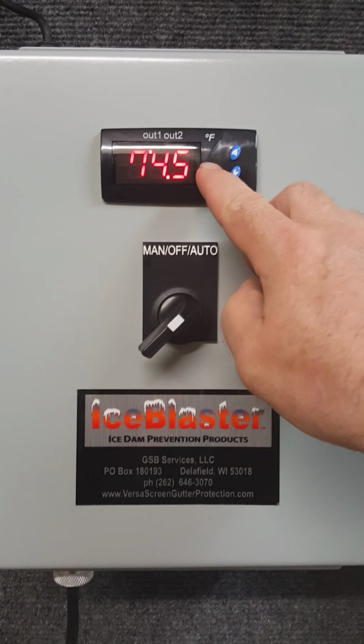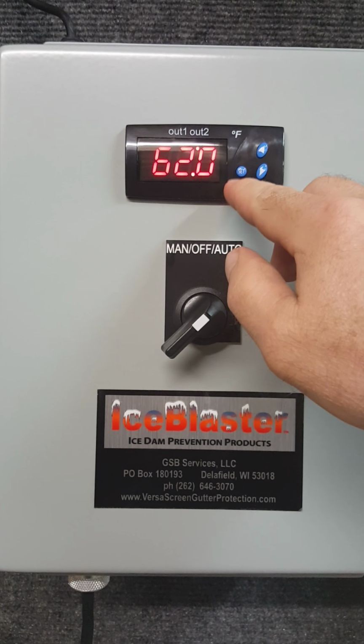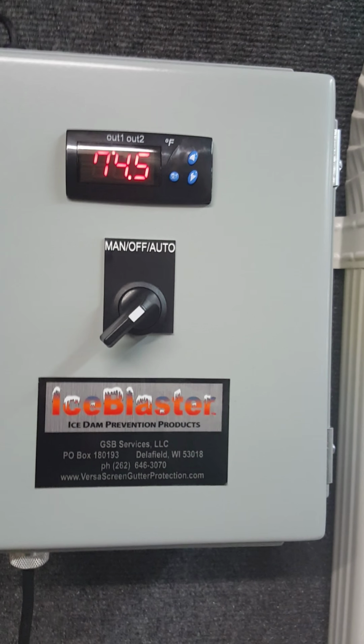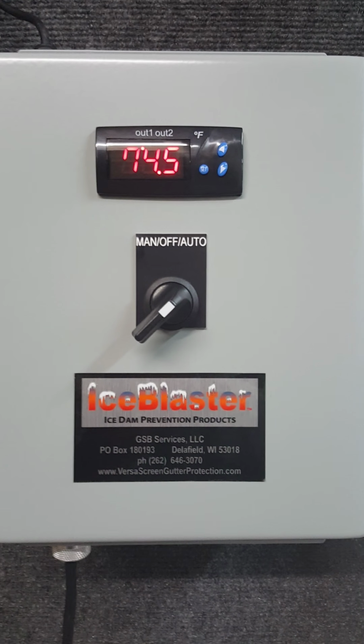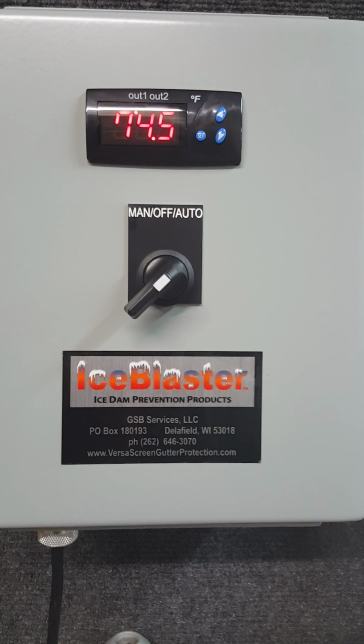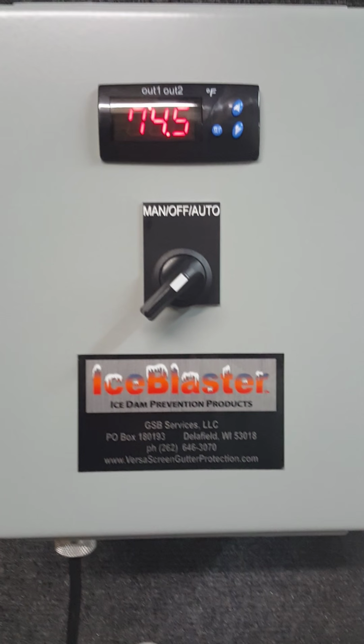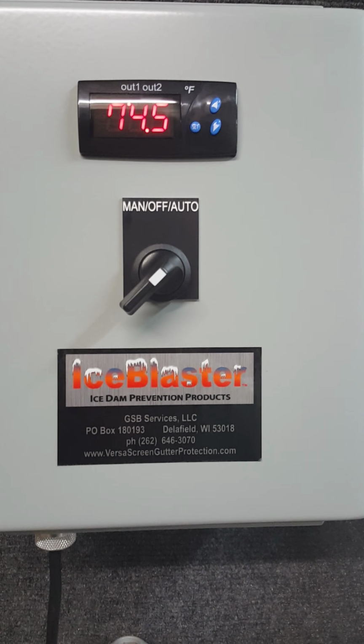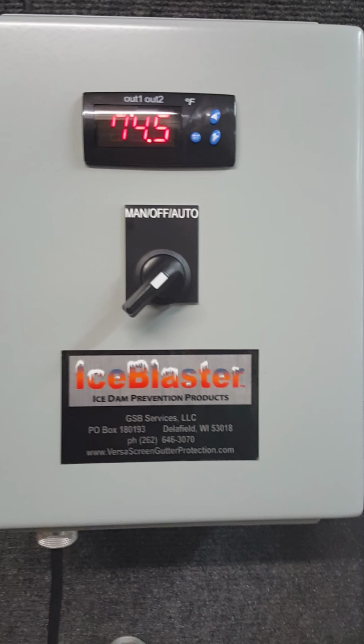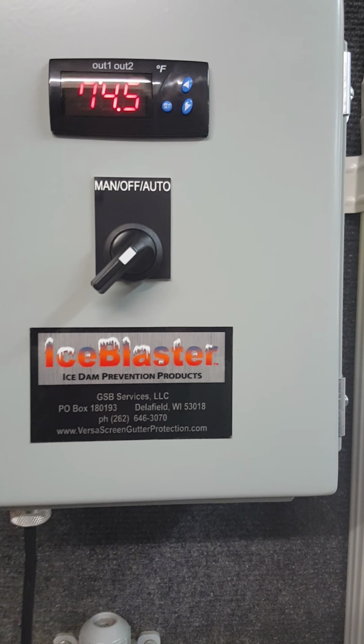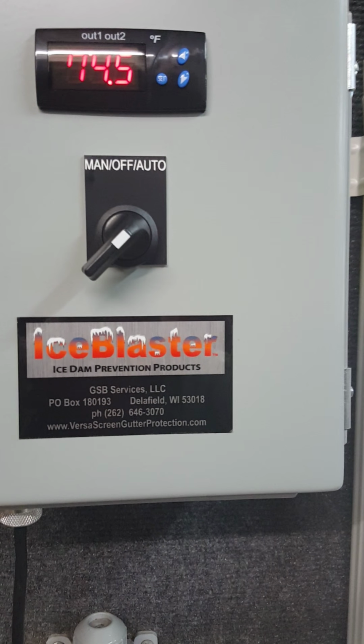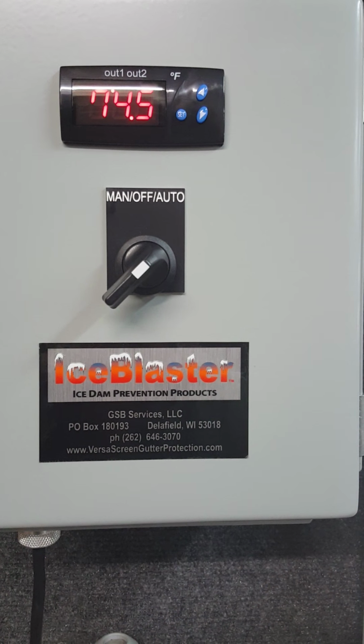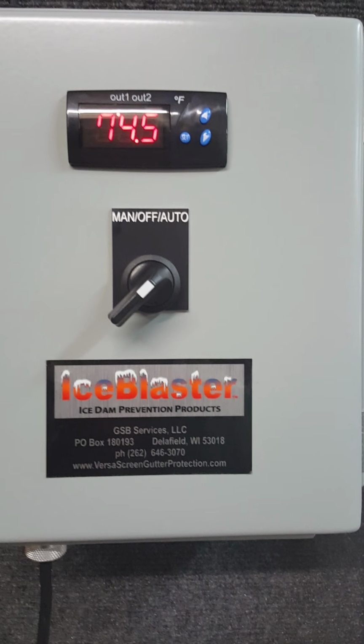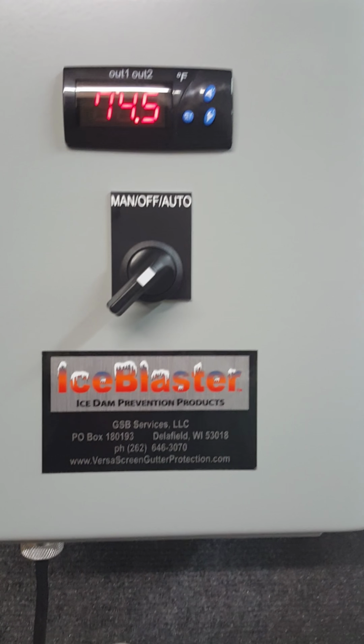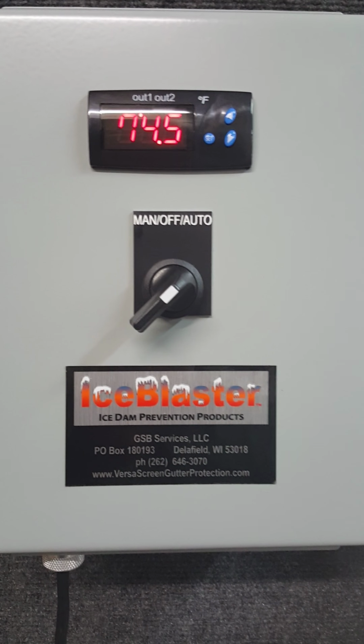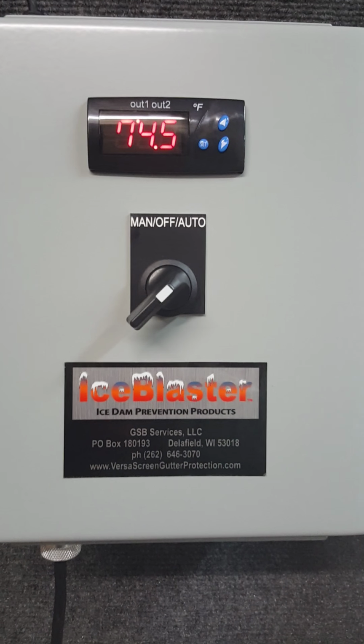It's got the great ability to adjust the temperature just depending on your circumstances, both the upper and the lower. When they come right from the factory, we're going to have them set for you at 37 degrees and 9 degrees. And we found in our experience with these systems, that's kind of a really good window to be at. You don't want to be down right next to freezing, because what can happen is, as the outside temperature warms, might have been 15 degrees at night, all of a sudden it gets to be 38 during the day. Well, it's warming up, it's going to turn the controller off because of the sensitivity of that probe, but the gutters may still be at 20, 25 degrees, so that meltwater is going to start refreezing in the gutter if this system isn't on. So that's why we have them set a little higher.